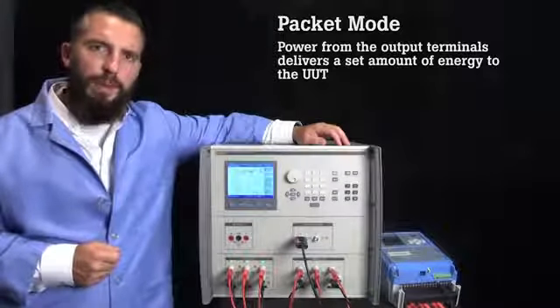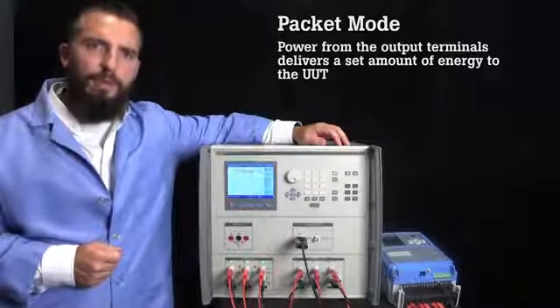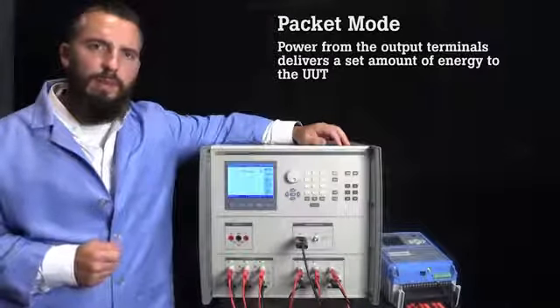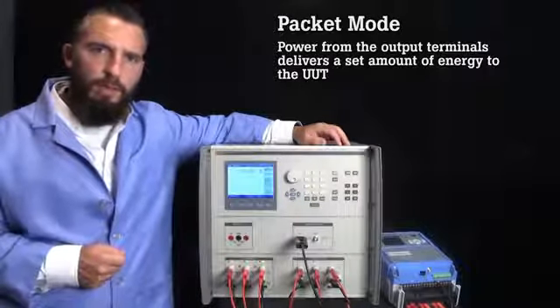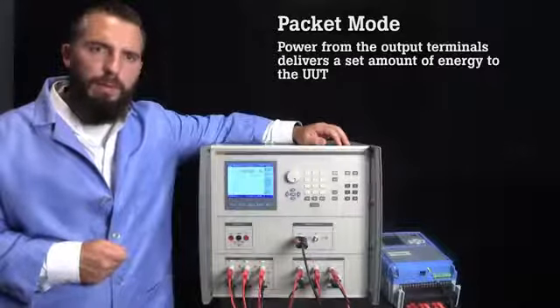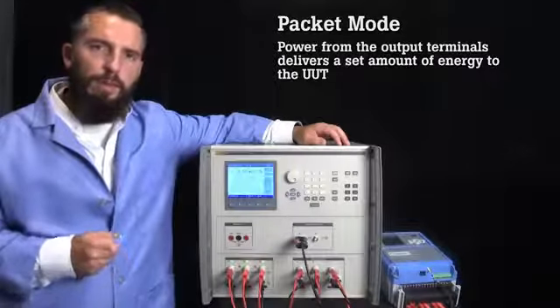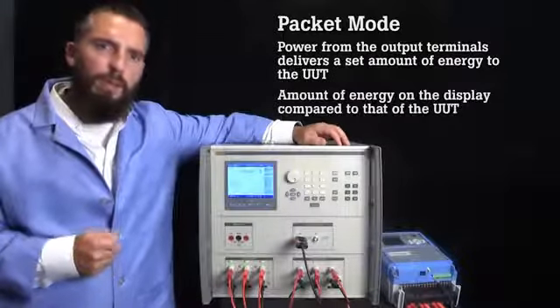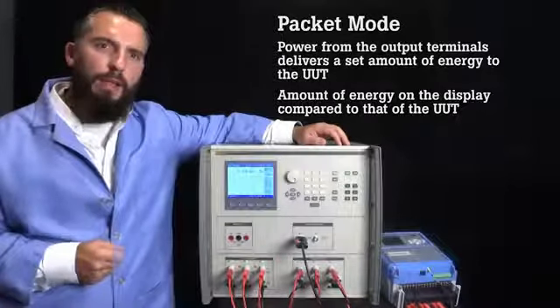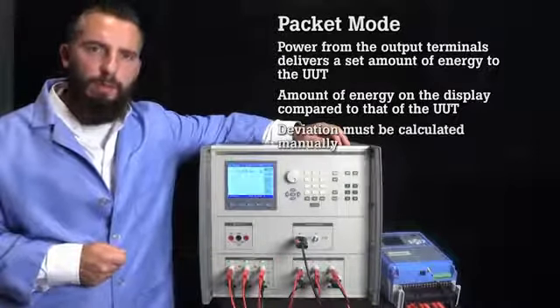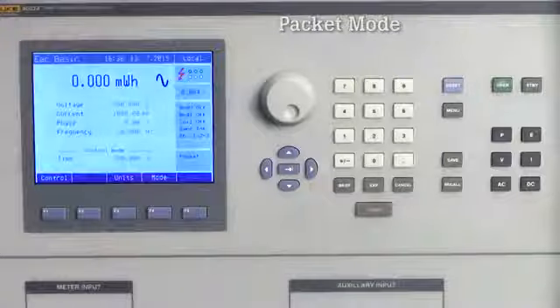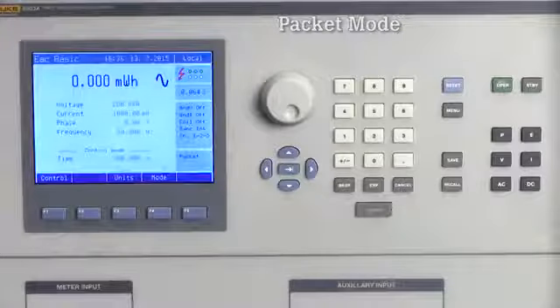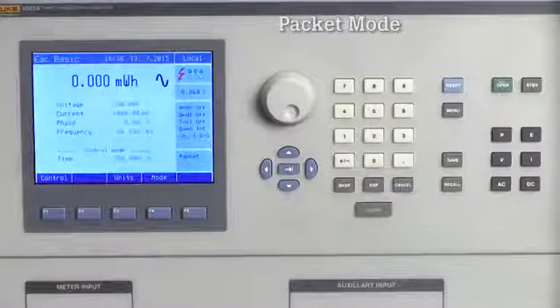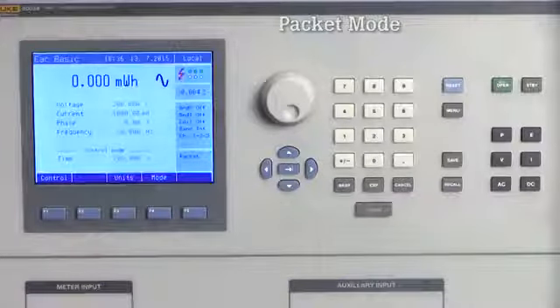This method is not as accurate as the other methods because the startup time of the 6003A is not synchronized with the UUT, but it is the simplest. To test the accuracy of the meter, the amount of energy shown on the display will be compared to that of the energy meter and the deviation must be manually calculated. Using this energy meter, I will run an example packet test which will let me determine if it measured and reported the correct watt hours.